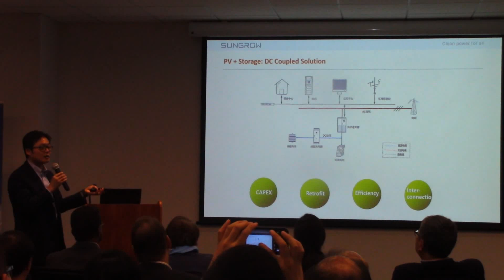Also about efficiency—because this only goes through one stage of conversion, not going back to the grid and back to the battery, you gain maybe 2 or 3% efficiency. So that's a return of 3% right away.